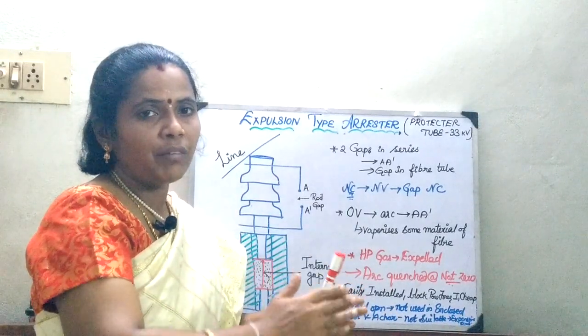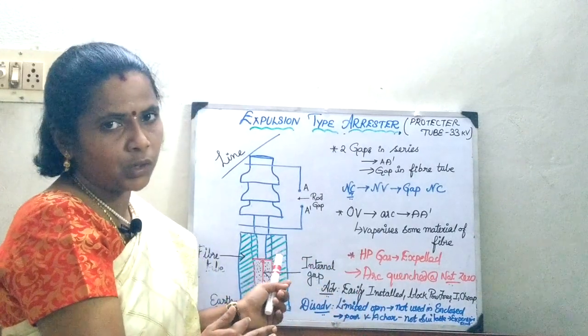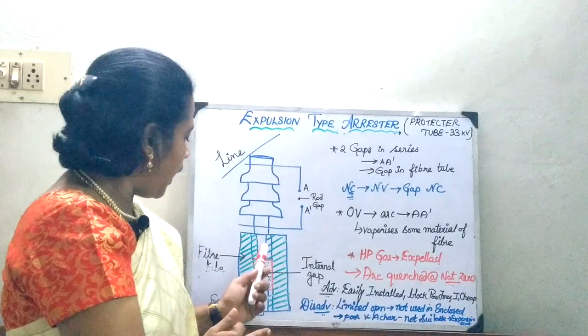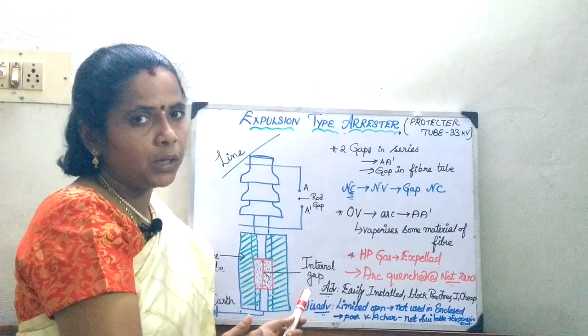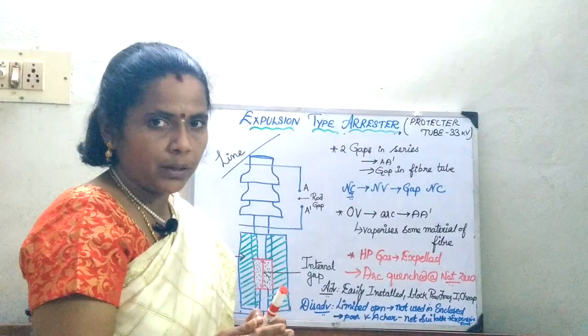The next thing - wherever you are going to have an enclosed equipment where I have to keep my lightning arrestor, in that condition, this cannot be used because a high gas discharge is going to be there. So, you cannot use it in the enclosed equipment.